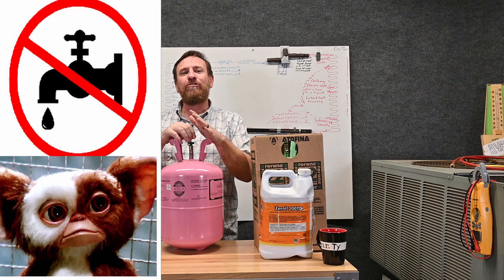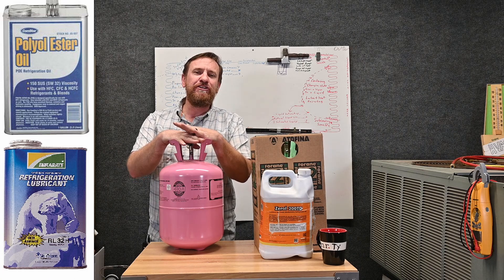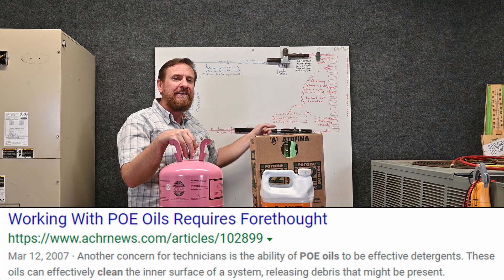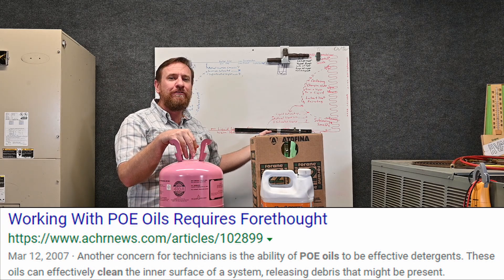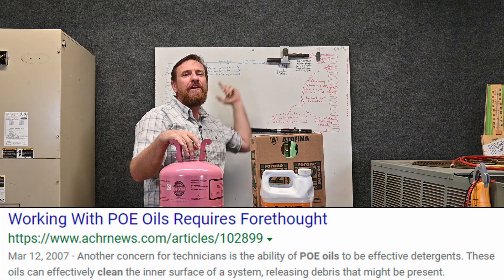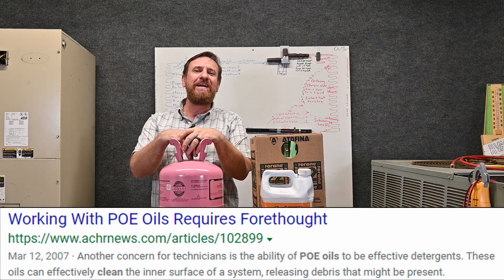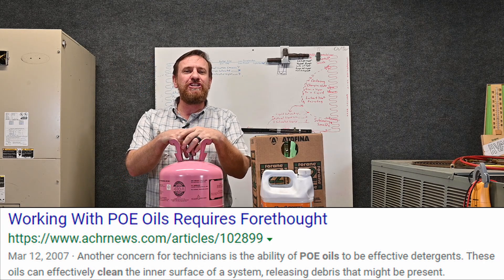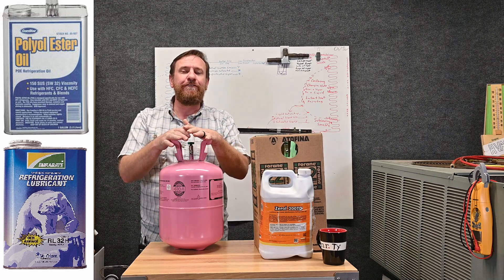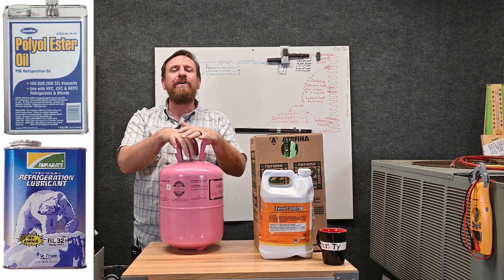Having a critically clean and dry system is important. The second thing is that polyol ester oil is also a cleaner — a great cleaner. So when we have oxidation left from not running nitrogen while we brazed, that oxidation on the pipes is cleaned off by this refrigerant. That sounds great, except we've cleaned it off all the piping and now it's flowing through the entire system, getting hung up in the compressor, filter dryers, and metering devices. So that oxidation is now an issue.